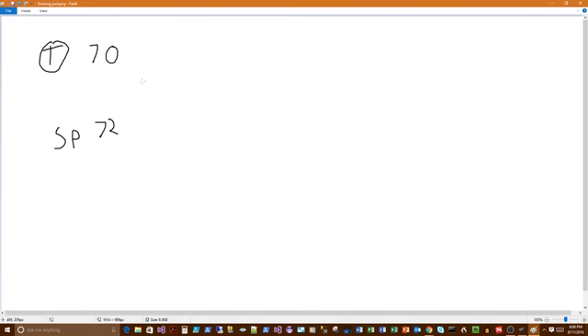Well, the difference between that is 2 degrees, and so a PID loop would say that that's considered error, right? There's a difference between temperature and the actual set point. Well, that 2 degree error is going to go into this control block. And this control block, called a PID loop, is going to have a proportional and an integral and a derivative, although in the building automation space we don't really use derivative.